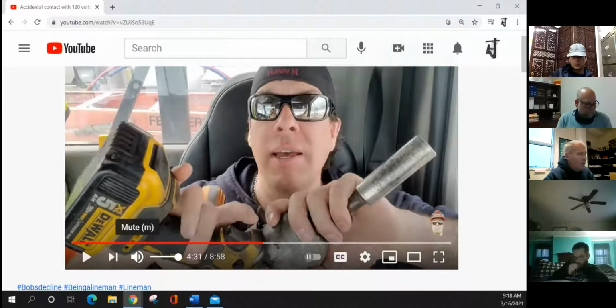And I've seen plenty of electricians - and man, this upsets me a good bit - that will walk up to a meter base, see something going on in there, and just stick their screwdriver in there, or a wrench or anything like that. If you need to work 120, 240 in a small space, de-energize it. Just a slip of the tool, and you're going to have a massive explosion right there in your face.